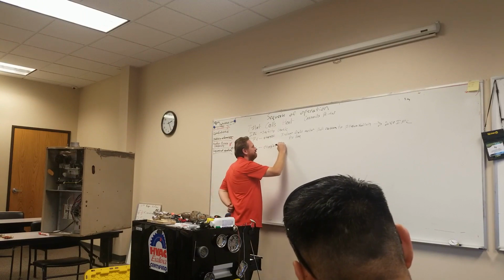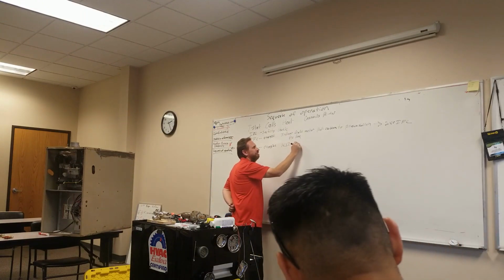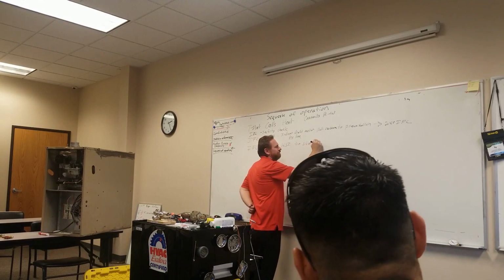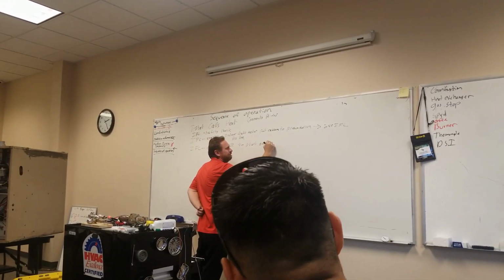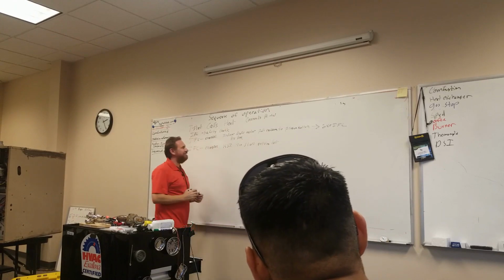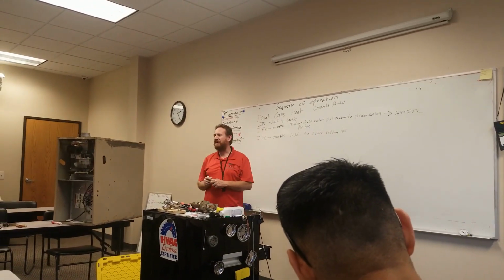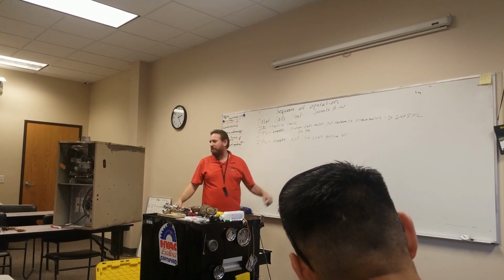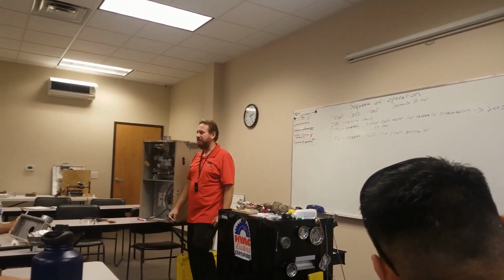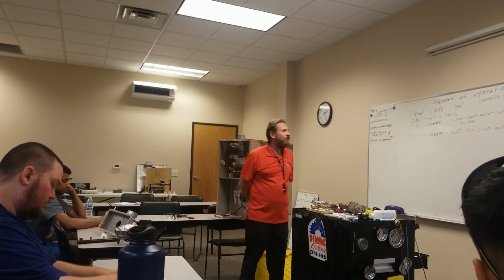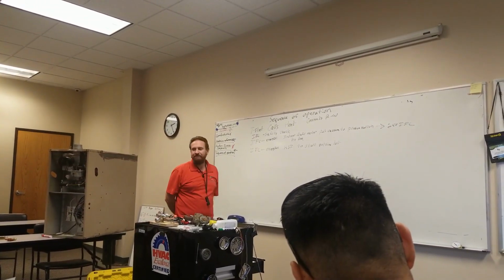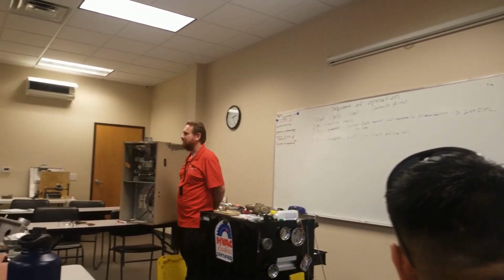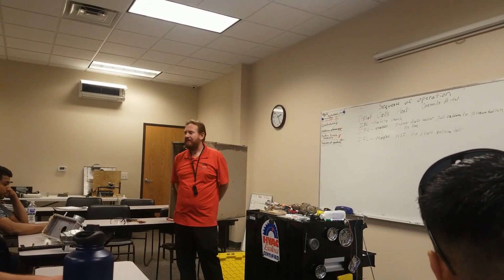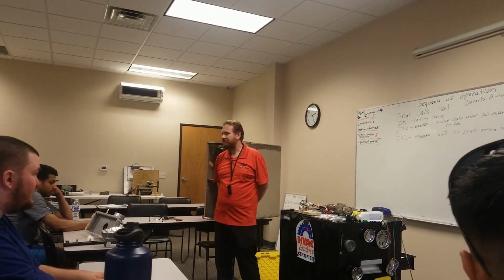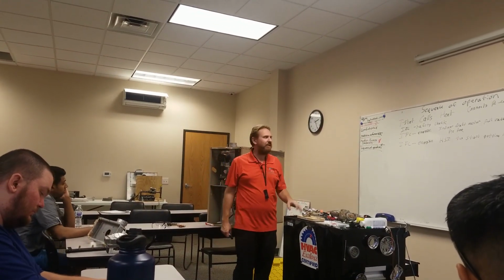What do you think? It's going to energize the HSI, hot surface igniter, to start getting hot. Or it can energize the spark igniter, either one. I think there are more HSIs than spark igniters, but it's going to either start sparking or start that hot surface igniter getting hot. Did that hot surface igniter get hot immediately when I plugged it in? It took just a few seconds, didn't it? So it's going to give it a little bit of a delay for that to get hot.